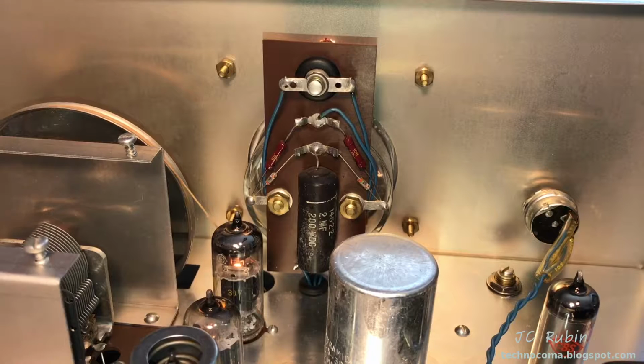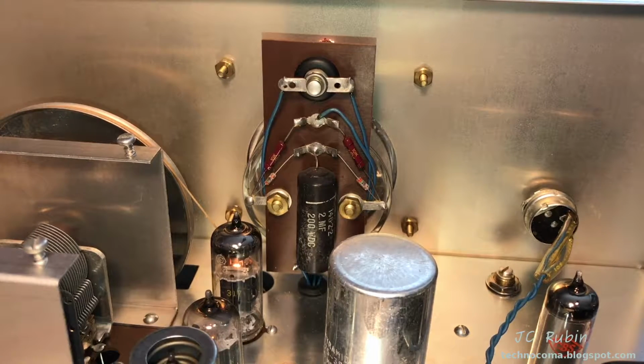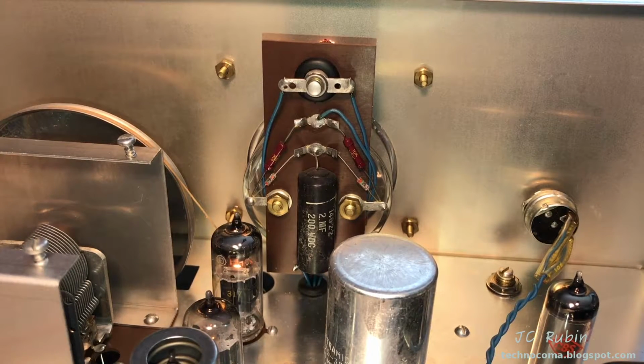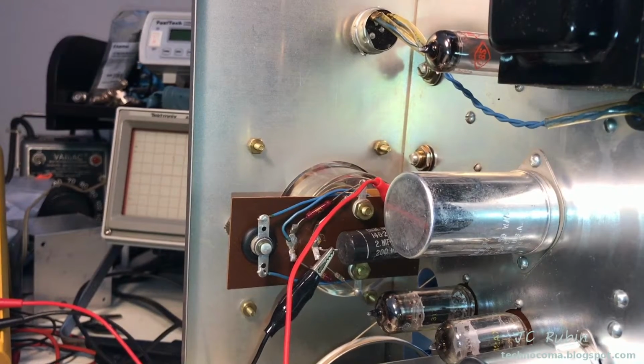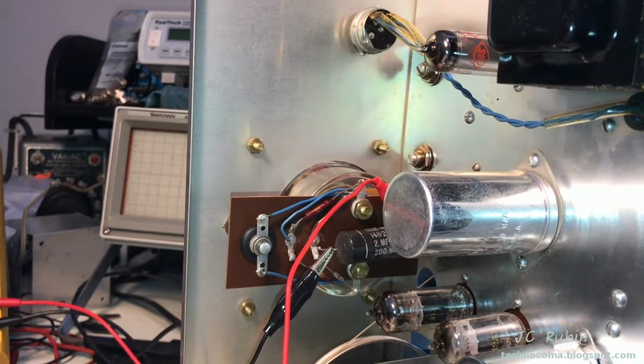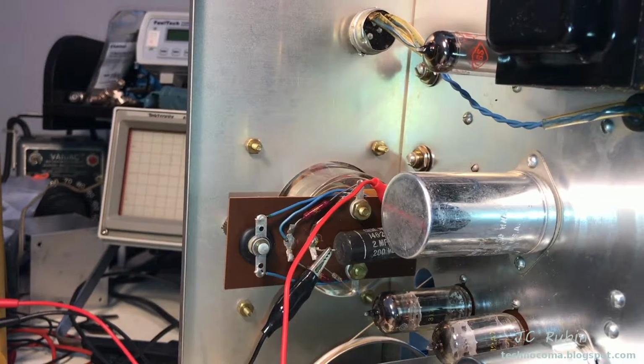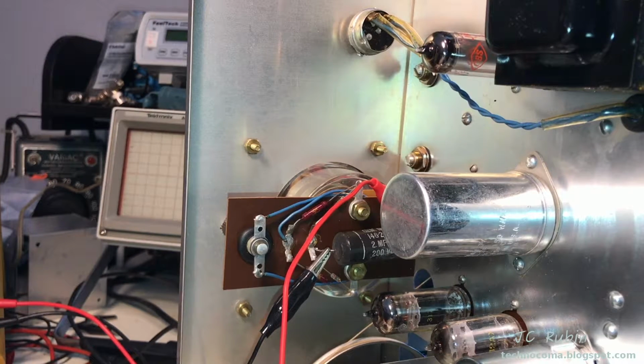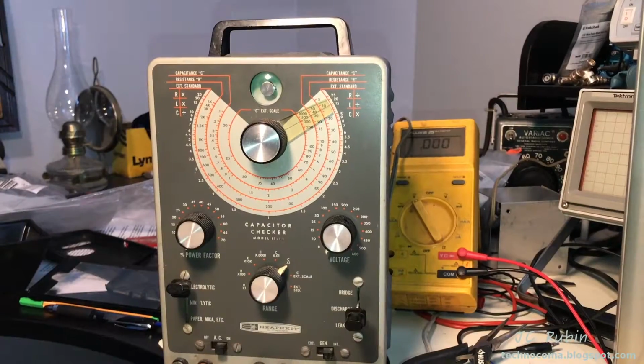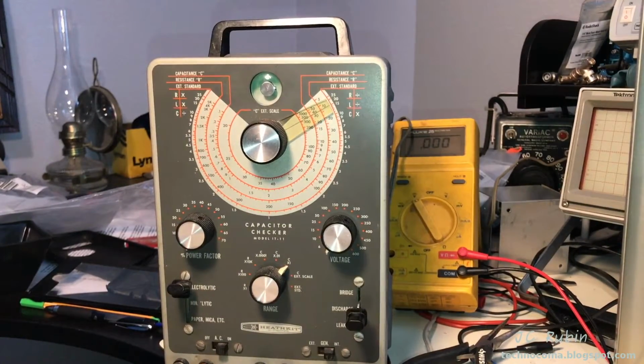How are we going to know? We're going to pull it out. We're going to hook it up to the IT11. We're going to see what's going on, and we'll replace it if we have to. All three of the capacitors have been pulled out of circuit, and they've been checked for their capacitance value, and all three of them tested really good, and now they're going to get a leak down test to make sure they're acceptable. For that, it's the same procedure. I've hooked them up to the IT11.